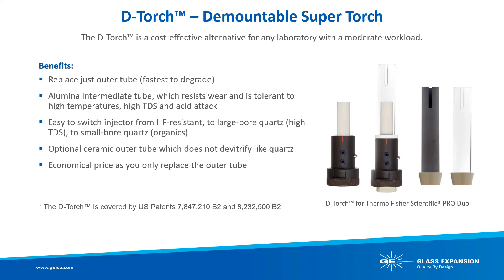Now that we have our nebulizer and spray chamber, this brings us to the torch. The ICP-OES torch is typically the most often replaced consumable with higher annual cost. Many ICP-OES manufacturers have moved to a demountable torch for this reason, and a semi-demountable torch provides more flexibility with a variety of injector options. Glass Expansion's patented D-torch is a high performance and economical alternative to the standard EMT torch, incorporating a ceramic intermediate tube for greater robustness and providing an outer tube that can be replaced when it fails rather than replacing the entire torch body.